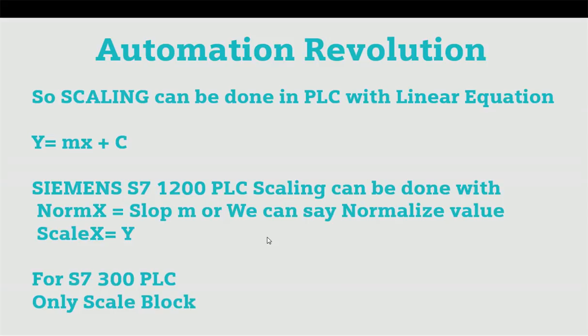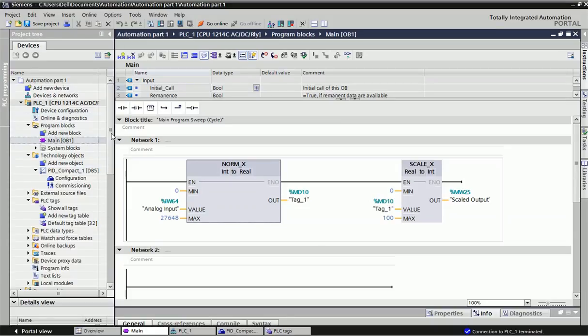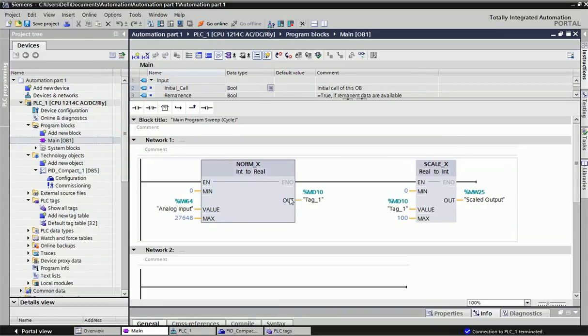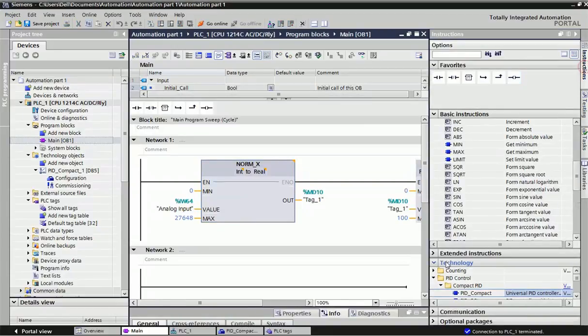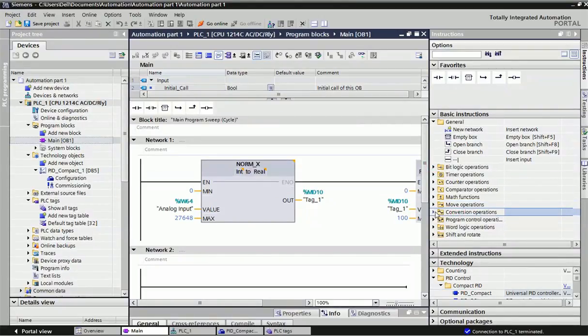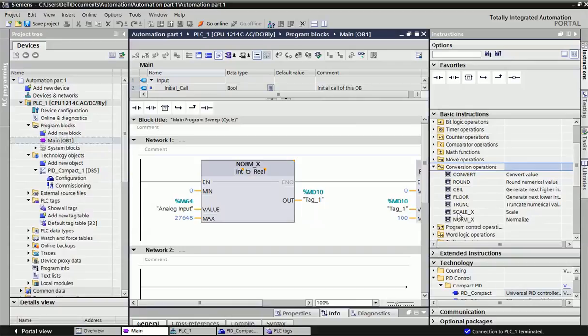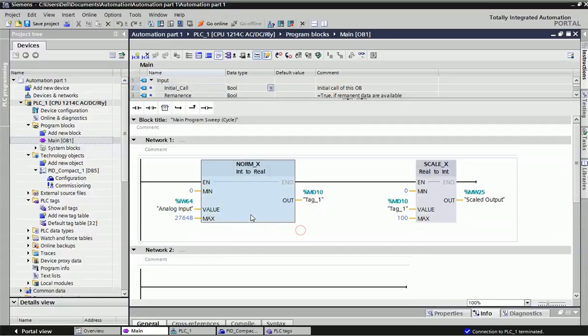Now we will see how we can assign in TIA Portal. Here I have taken S7-1200 series PLC. As I said, we will use two types of blocks: NORM_X block and SCALE_X block. These blocks you will get from basic instruction, conversion operations. From the conversion operations you can see two blocks: NORM_X and SCALE_X. Or you can take an empty box and just type NORM_X to get the block.